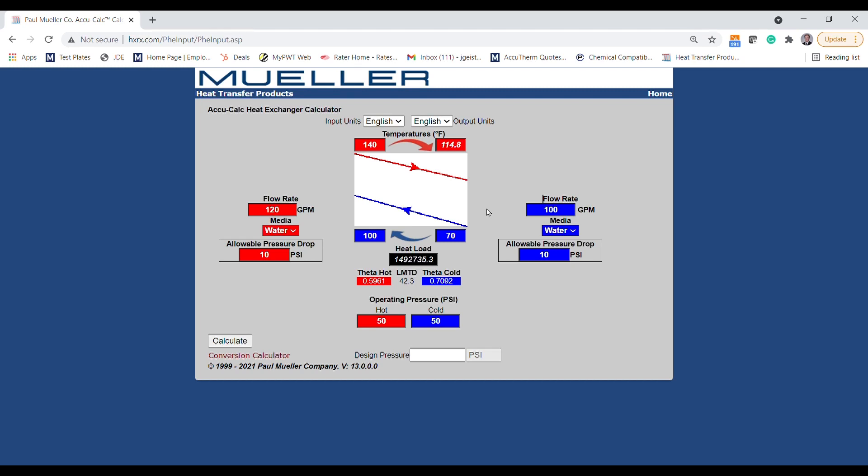With our thermal requirement selected, we also have to enter a maximum pressure drop that we're going to allow. The default is 10 psi for both fluids, and we typically do not recommend dropping below 5 psi. These pressure drop values can sometimes influence the final sizing even more than the thermal requirement, so you want to make sure that you're not oversizing your heat exchanger by selecting too low of a pressure drop.